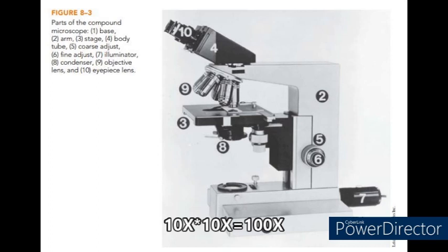The maximum useful magnification of a compound microscope is approximately 1000 times the NA of the objective being used. This magnification is sufficient to permit the eye to see all the detail that can be resolved. Any effort to increase the total magnification beyond this figure will yield no additional detail and is referred to as empty magnification. Although a new student of the microscope may be tempted to immediately choose the highest magnifying power available to view a specimen, the experienced microscopist weighs a number of important factors before choosing a magnifying power.